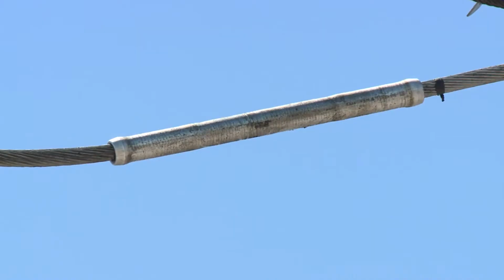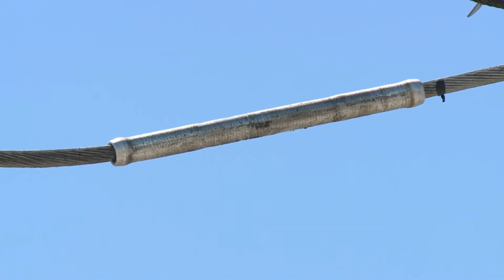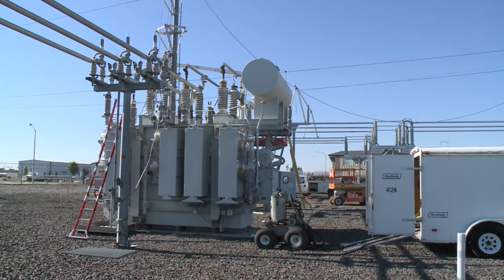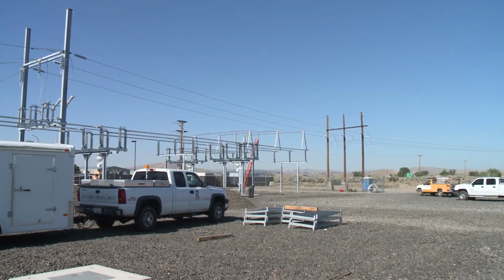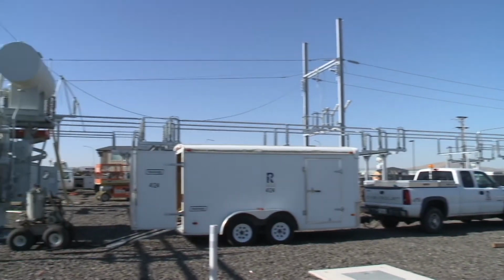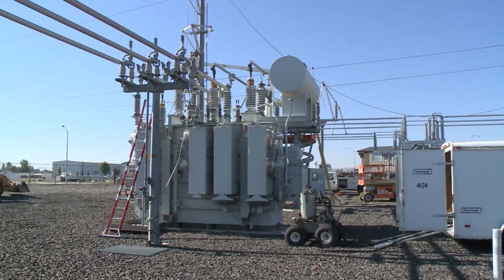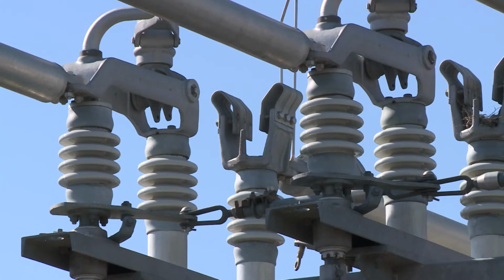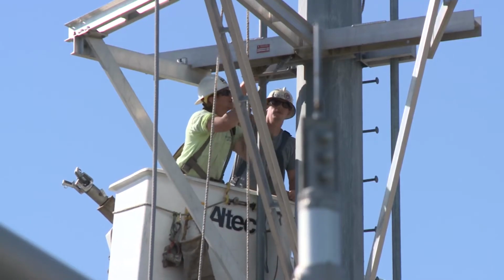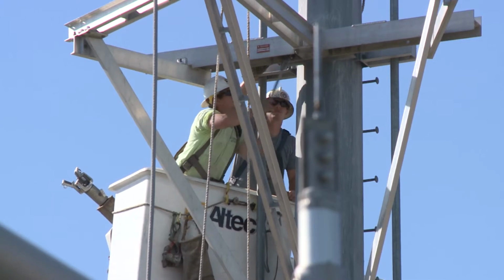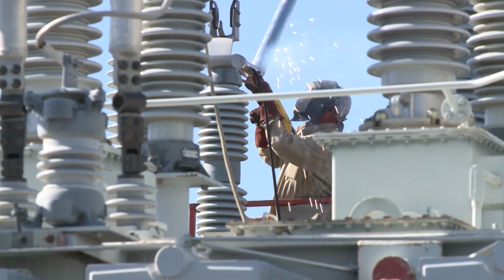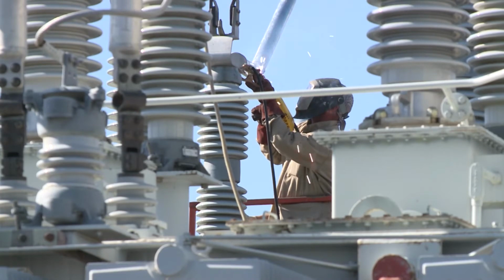Back in 1988, when the substation was originally commissioned, the plan was for it to serve loads in this region, with the capability of containing four power transformers. Inside the substation there's a transformer and switchgear—think of the switchgear as the panel board of a typical house. The transformer steps the voltage down from the 115,000 volts that the city's transmission line is energized at, down to 12,470 volts.